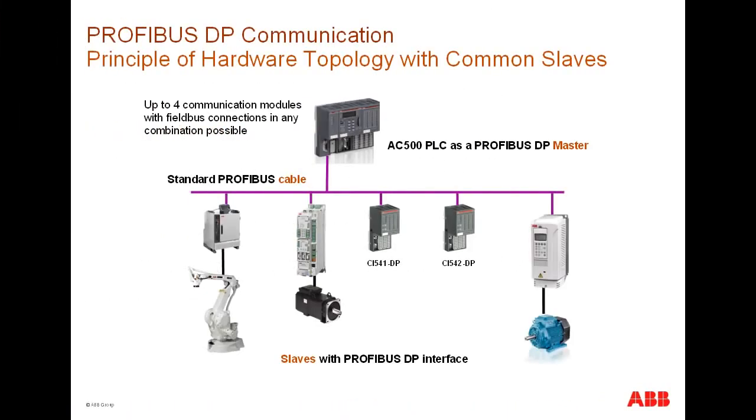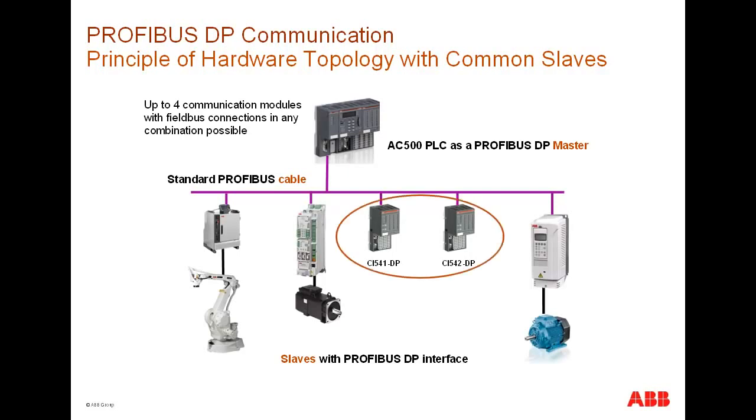Here you could see an example of how to connect a DP slave to a PROFIBUS DP master. The CM572 module mounted just left to the CPU is acting as a PROFIBUS master. Up to four DP masters could be connected to one CPU, and in this way, we could establish four independent PROFIBUS lines. In this example, an ABB robot, one ABB drive, and two S500 bus modules are used as PROFIBUS slaves. They are connected to the DP master CM572 module using the standard PROFIBUS cable and appropriate connectors.